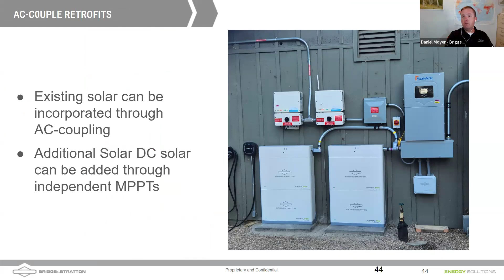We've now, instead of using gen input as load output, we've checked for AC coupled input into gen. We need to make sure that grid sell is enabled. And notice these numbers got flip-flopped, right? So, the long story short is AC coupled solar, if it's producing AC, it has to have somewhere to go. And the Sol-Ark, when it's grid forming, can use frequency adjusting to curtail the production of AC microinverters or a string inverter. But we want to turn that AC coupled solar off before the batteries get full.